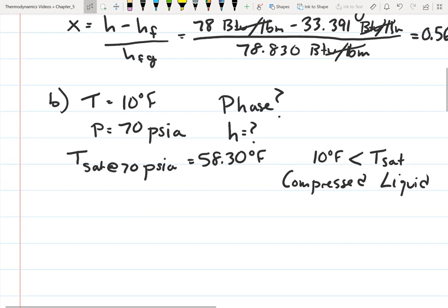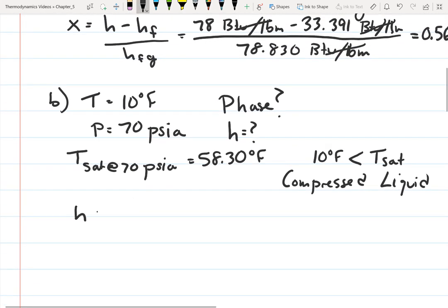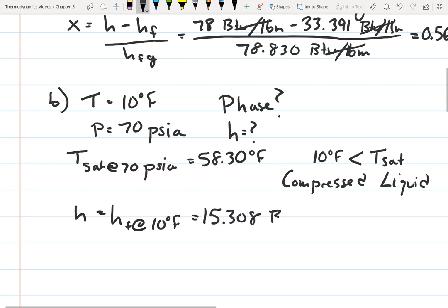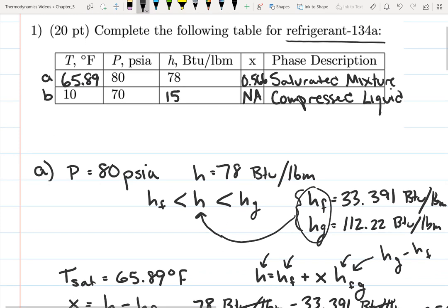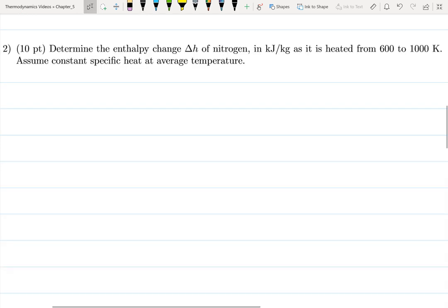Looking at the saturated refrigerant 134a temperature table, at 10°F the enthalpy of the saturated liquid is 15.308 BTU/lbm. We look this up at the temperature, not the pressure. So the enthalpy for state B is 15.308 BTU/lbm.